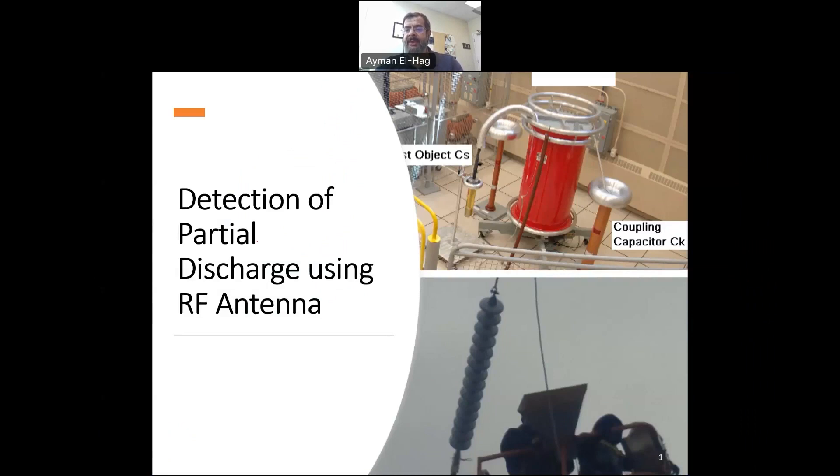In a recent video, I talked about how we can detect partial discharge using the classical PD setup with some demo. Now this technique is very sensitive, and we would see in the demonstration after this short presentation that the classical PD setup is much more sensitive than the RF antenna to detect partial discharge.